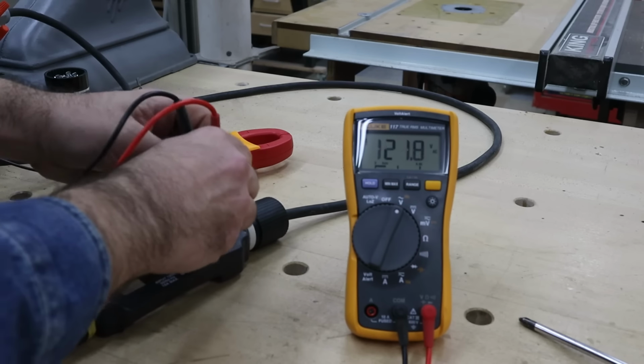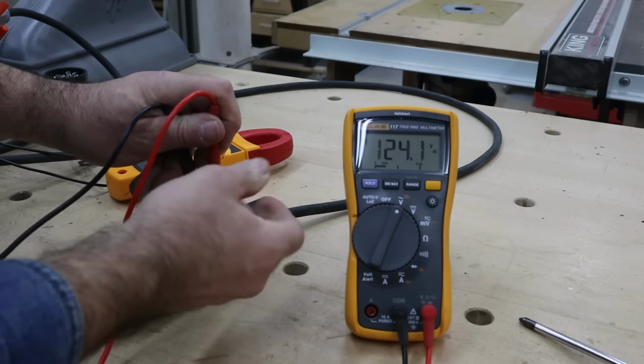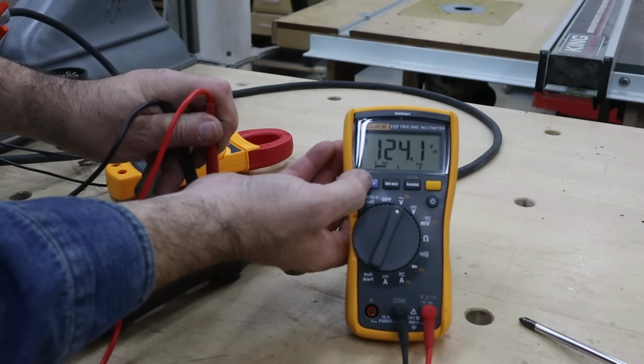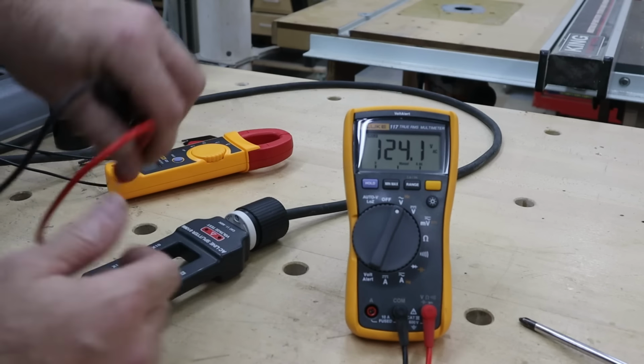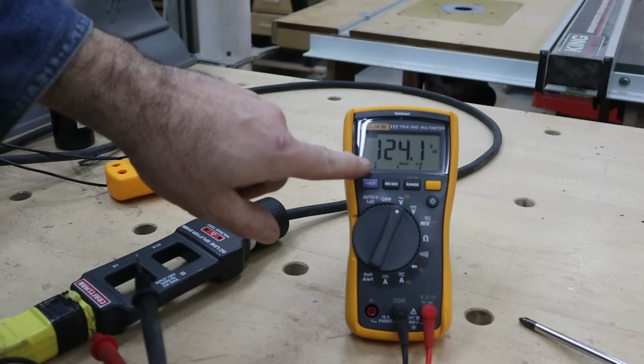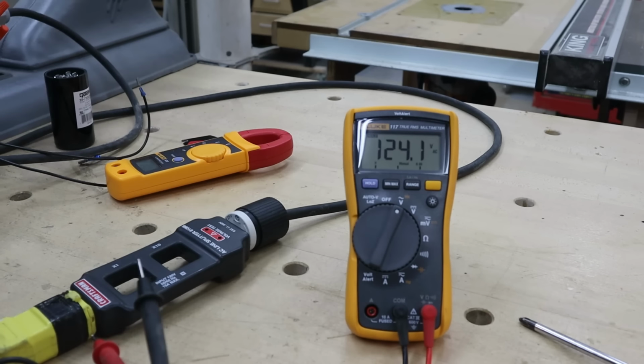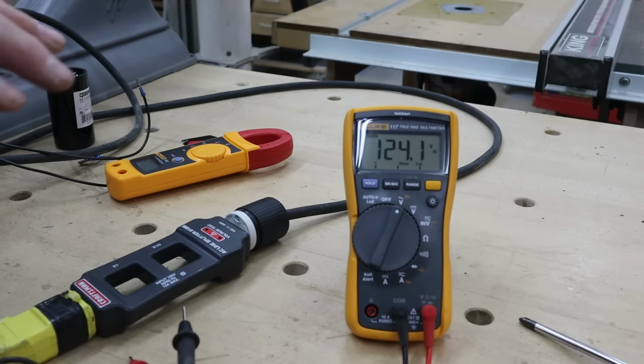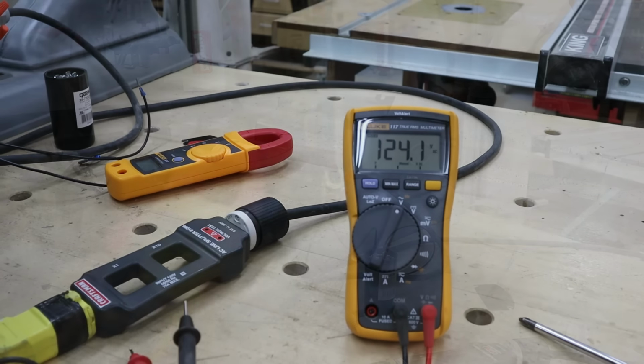So if I take a reading, and we're going to hit the hold function. So currently, when I turn on the power, the motor is going to be fed with 124 volts. Now that's slightly higher than the 115 volt rating that we found on the motor's rating plate, and that's going to affect the current as well as the power factor.